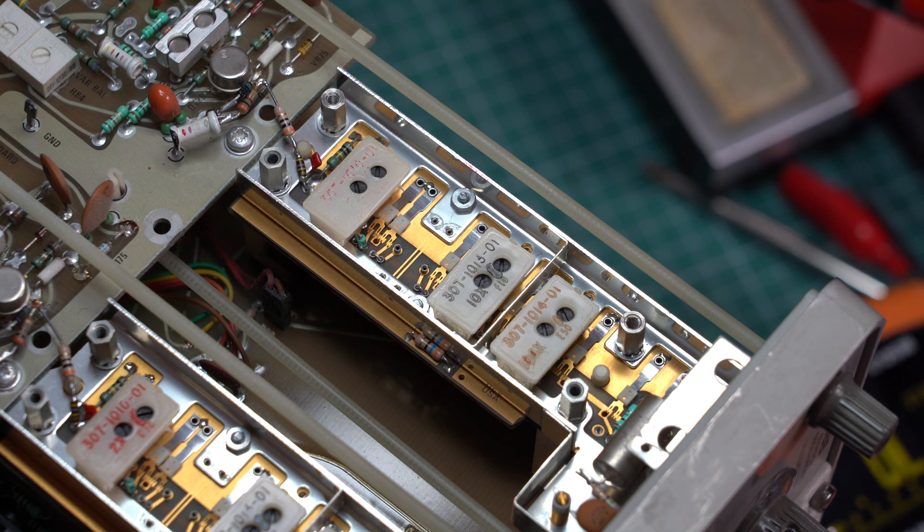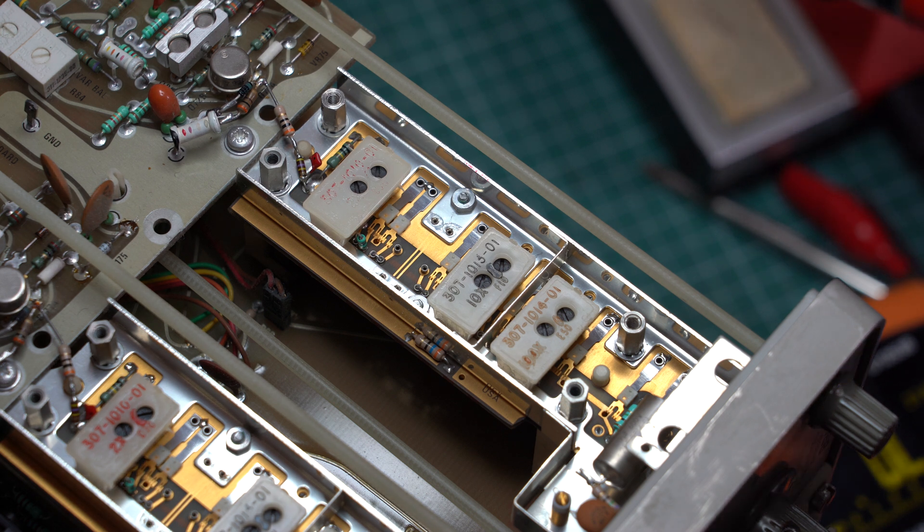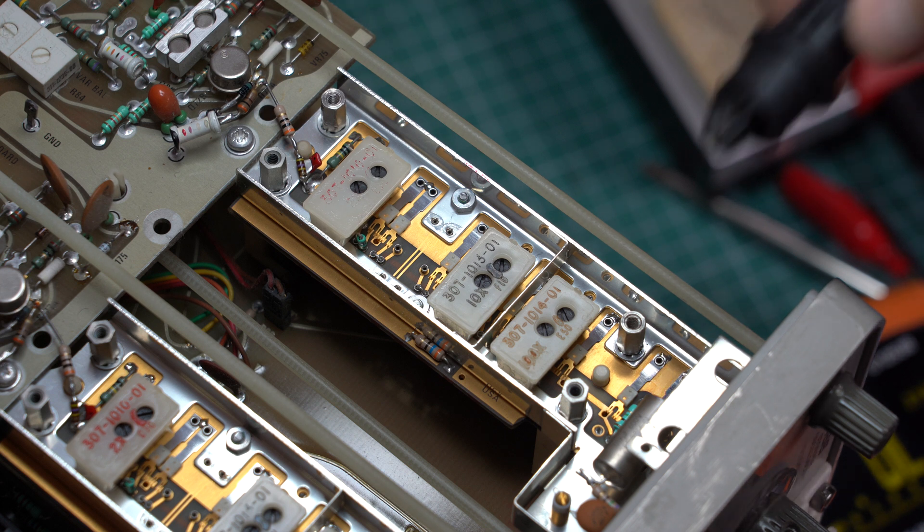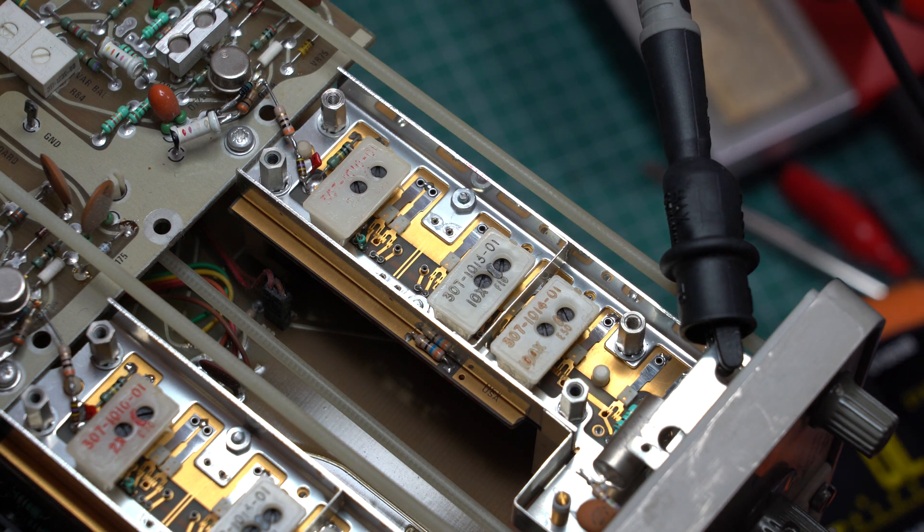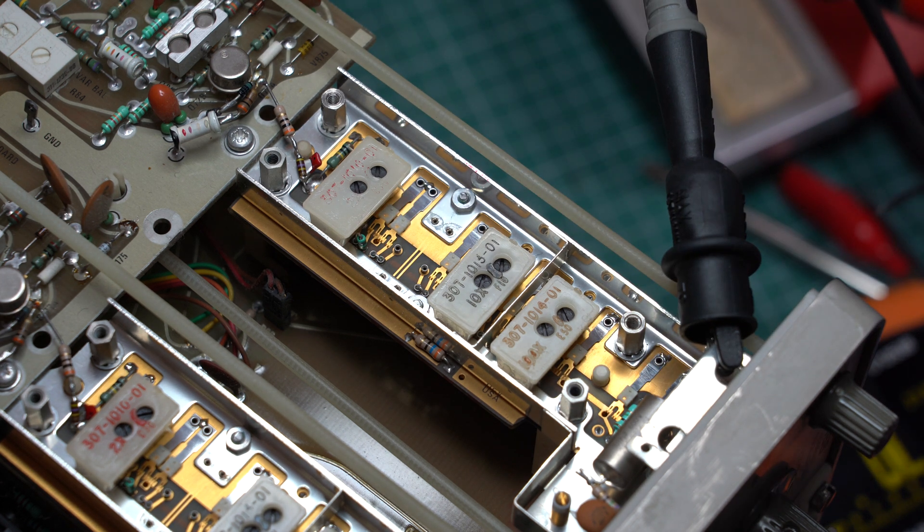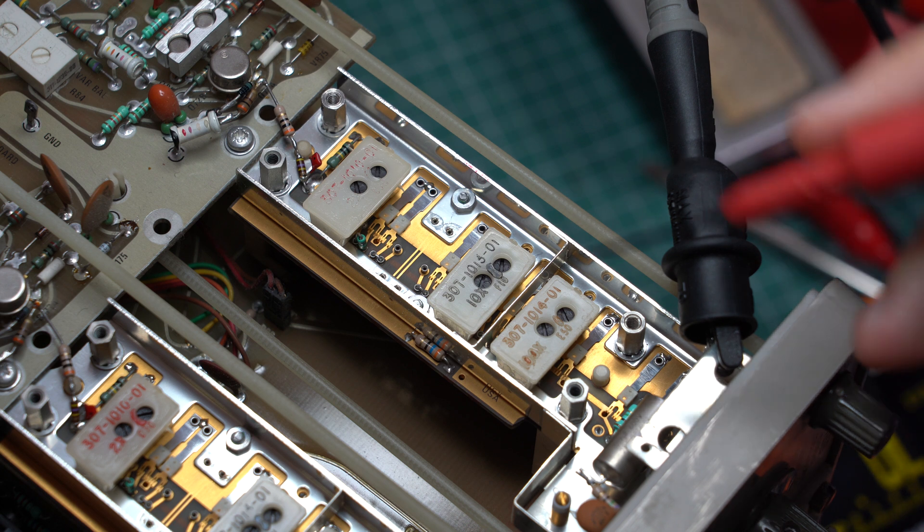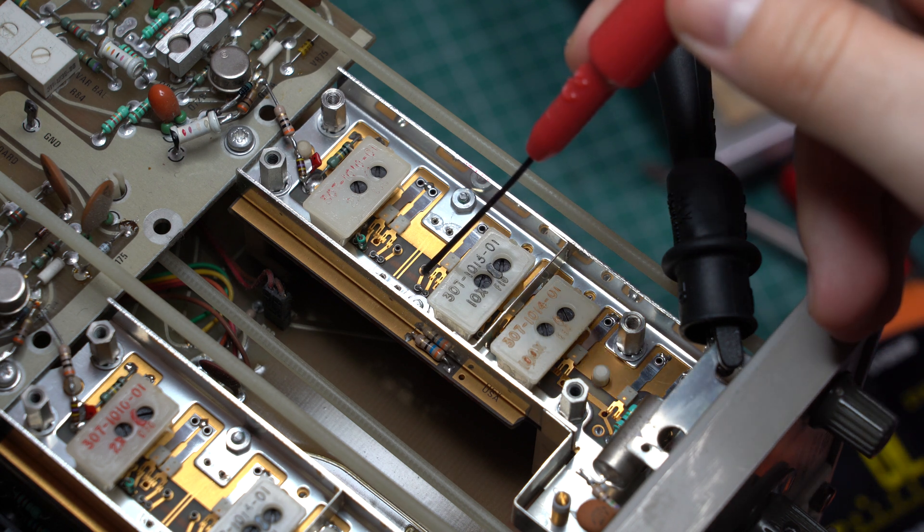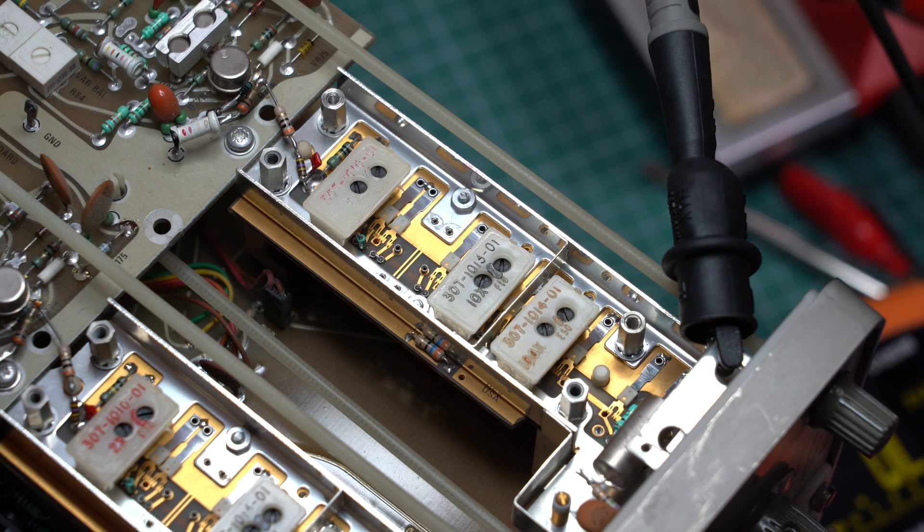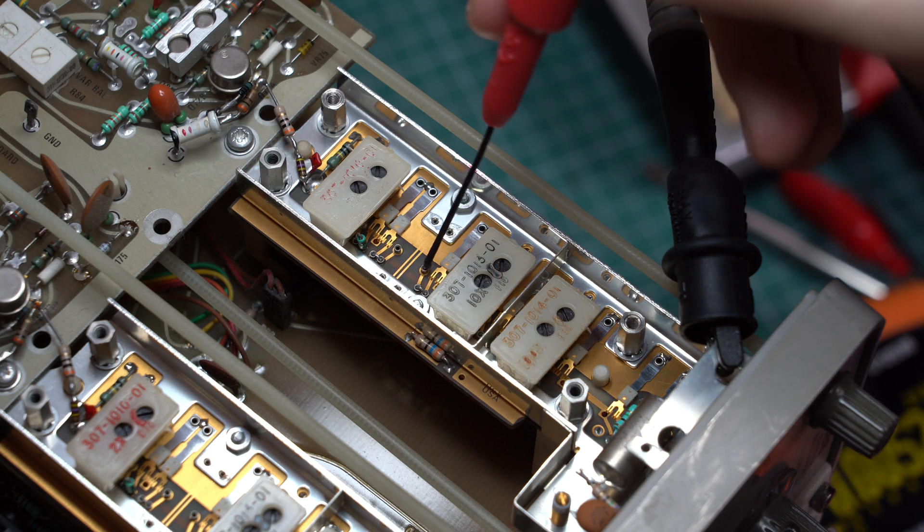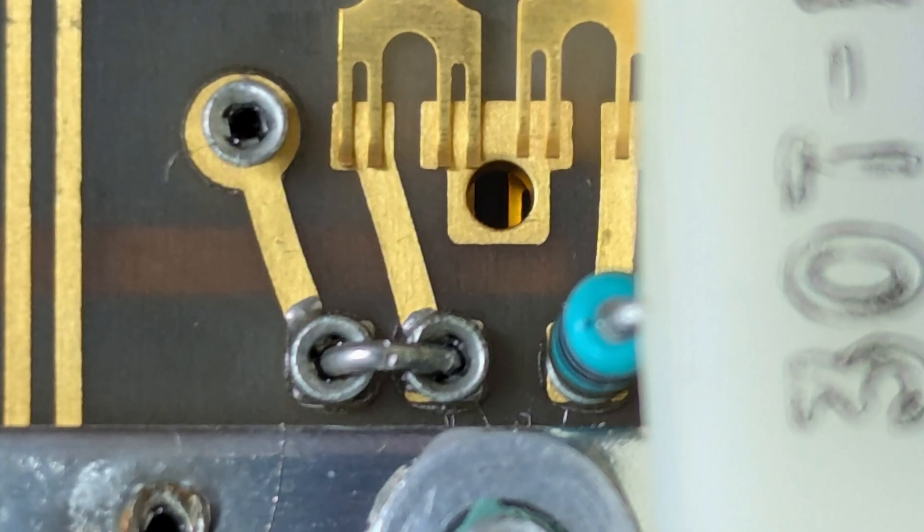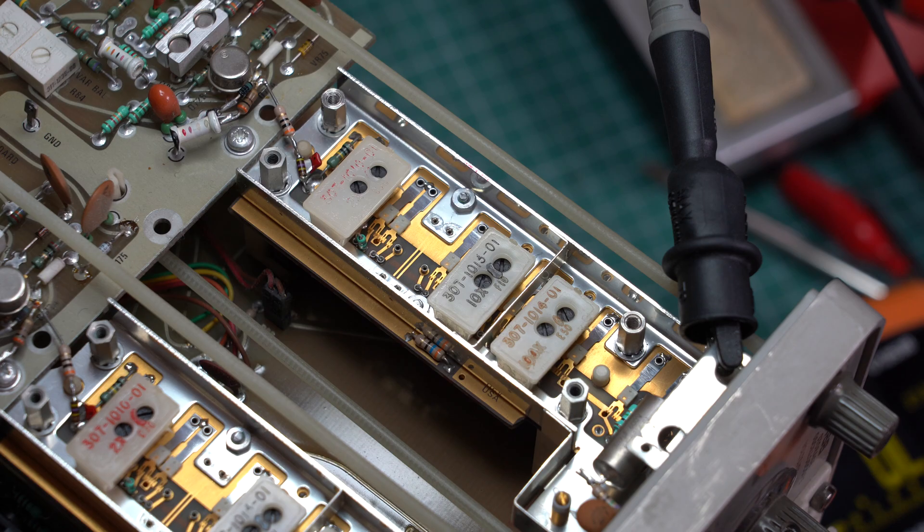Let's see. First of all, let's ground the meter to the chassis. It looks like we have some tin whiskers between this nut and the pad that connects to the attenuator. So here it is. It's a dead short. So one way to figure it out is to have a look at the resistance. And in the case of this oscilloscope, by the way, when you perform this test, the input selector needs to be to DC.